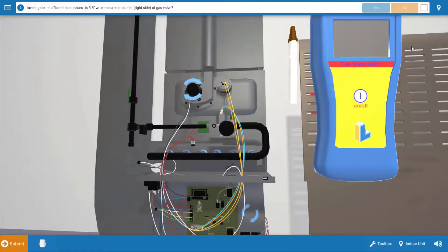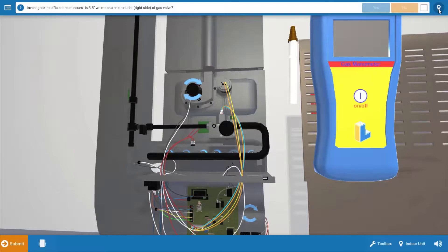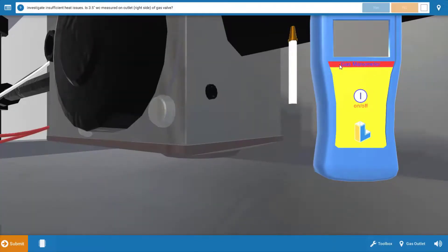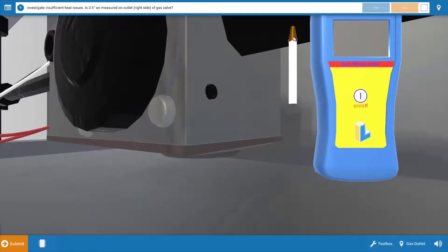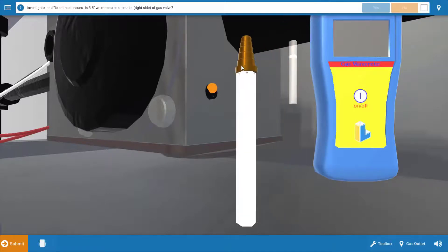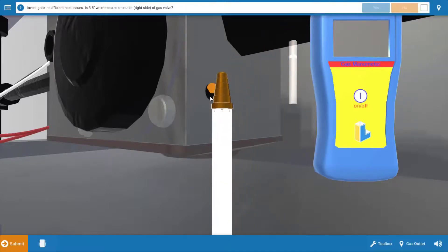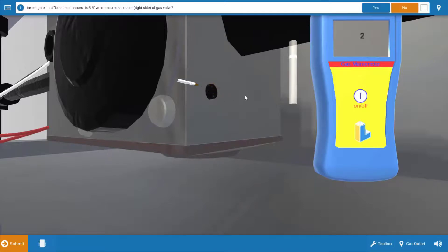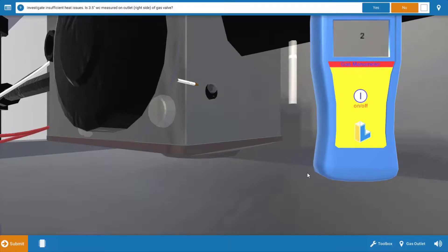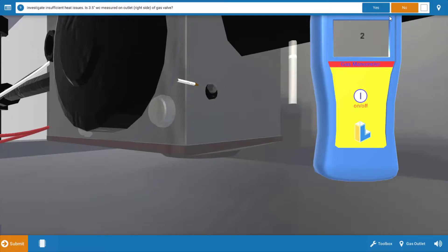Our next step is to check fuel input. So we're going to click on this teleport icon and go back and take out the digital gas manometer and measure the gas pressure in inches of water column at the manifold or burner side of the gas valve. This should be three and a half inches of water column. So we're going to drop our manometer here, and when we do this, we only have two inches of water column, which is unusually low. It's pretty standard on natural gas appliances to have three and a half inches of water column here on the manifold side or burner side of the gas valve. So do we have three and a half? Well, no, we don't.